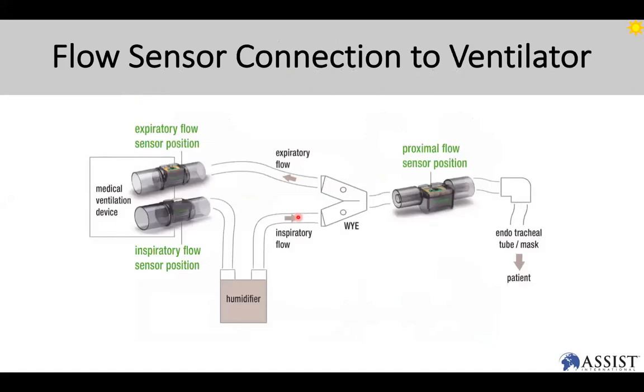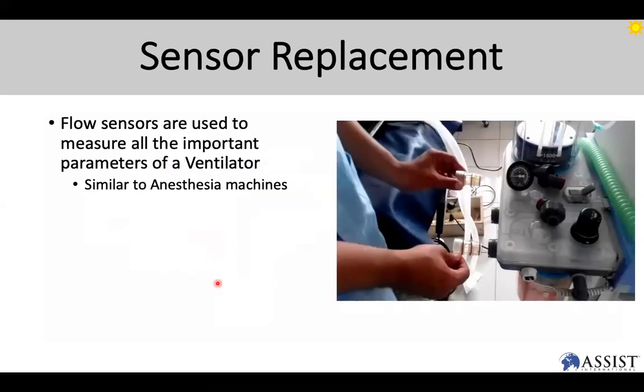Here are some pictures that'll help you visualize it better. So from the ventilator, you'll have an inspiratory flow sensor. And if there's a humidifier in the circuit, you may not have a humidifier, but if there is, it'll go to the humidifier out towards the Y-piece. And between the Y-piece and the patient, you will see the proximal flow sensor that looks something like this. And from the expiratory side of the Y-piece, you trace the limb back to the vent and you'll see an expiratory flow sensor. The flow sensors are used to measure all of the important parameters of a ventilator. These are extremely key sensors, and they're very similar to an anesthesia machine.